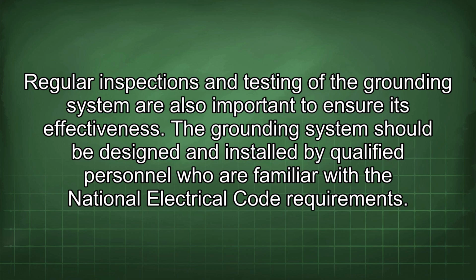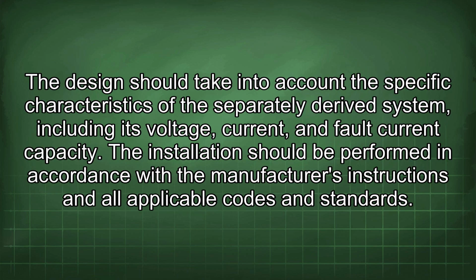The grounding system should be designed and installed by qualified personnel who are familiar with the National Electrical Code requirements. The design should take into account the specific characteristics of the separately derived system, including its voltage, current, and fault current capacity. The installation should be performed in accordance with the manufacturer's instructions and all applicable codes and standards.